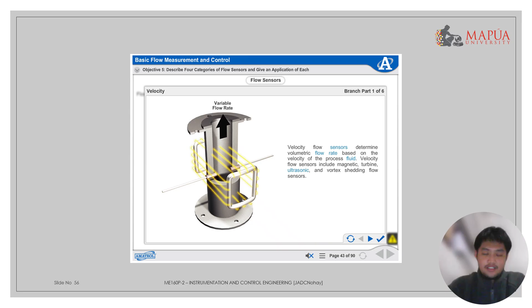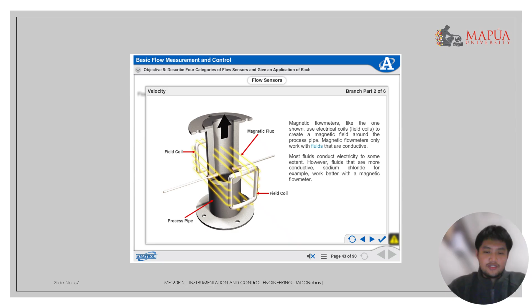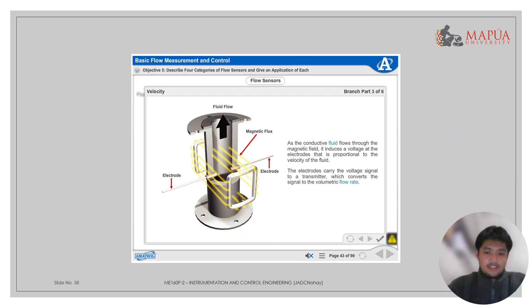Magnetic flow meters like the one shown use electrical coils, field coils, to create a magnetic field around the process pipe. Magnetic flow meters only work with fluids that are conductive. Most fluids conduct electricity to some extent. However, fluids that are more conductive, sodium chloride, for example, work better with a magnetic flow meter. As the conductive fluid flows through the magnetic field, it induces a voltage at the electrodes that is proportional to the velocity of the fluid. The electrodes carry the voltage signal to a transmitter which converts the signal to the volumetric flow.